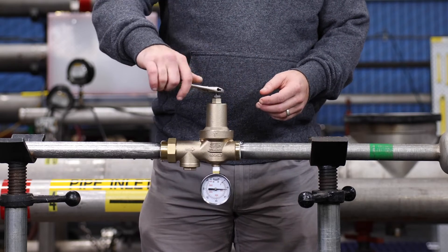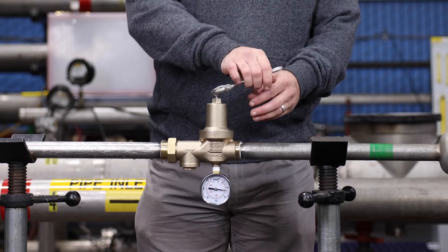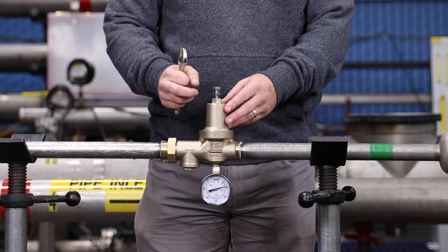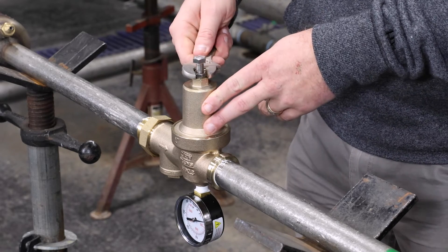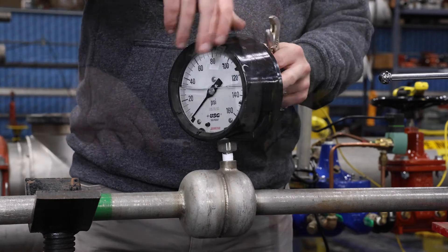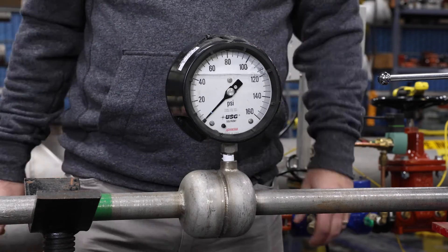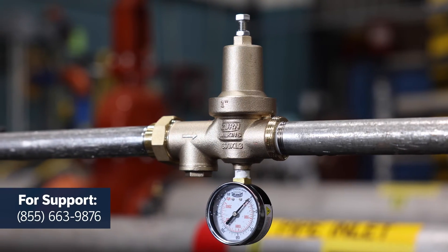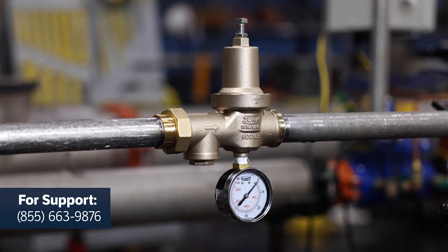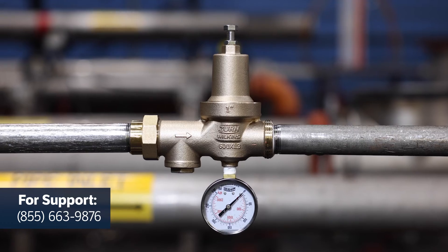Adjust the pressure to your desired outlet pressure by turning the adjustment bolt clockwise to raise the pressure or counterclockwise to lower the pressure. Tighten the lock nut when the desired pressure is achieved. Using a pressure gauge, retest the valve to confirm proper operation as outlined in the testing section of the 600XL3 testing manual. And that's it — thanks for watching. We hope you found this information useful. If you need additional support, please reach out to our Zurn customer care team. For other installation and troubleshooting videos, visit Zurn's YouTube channel.